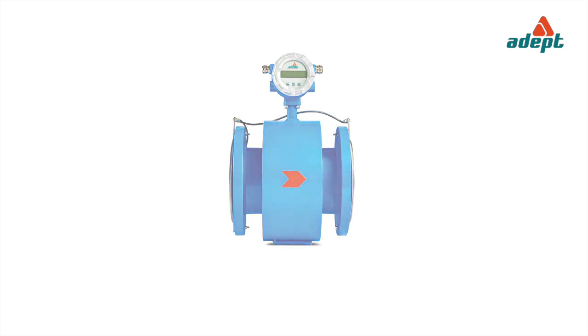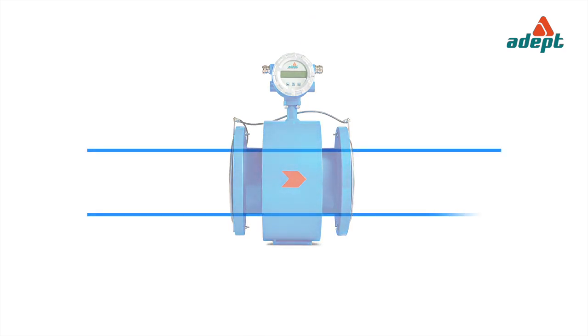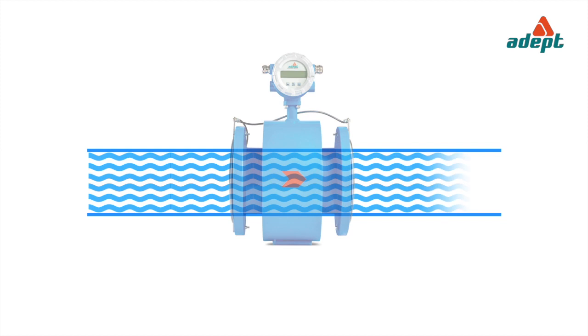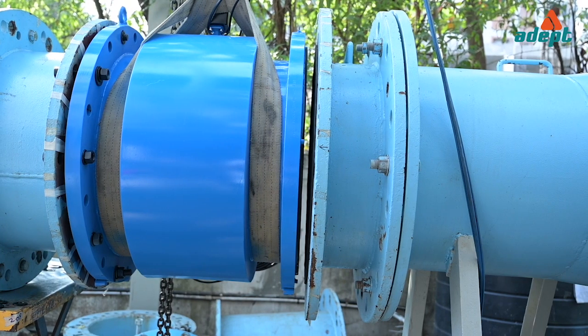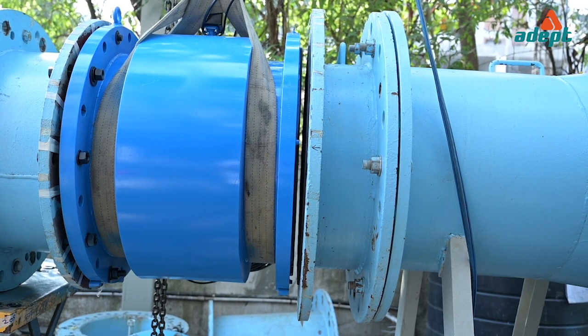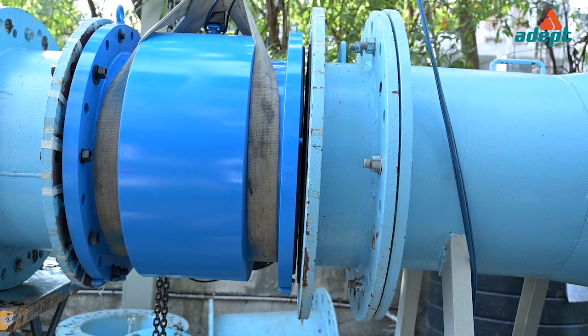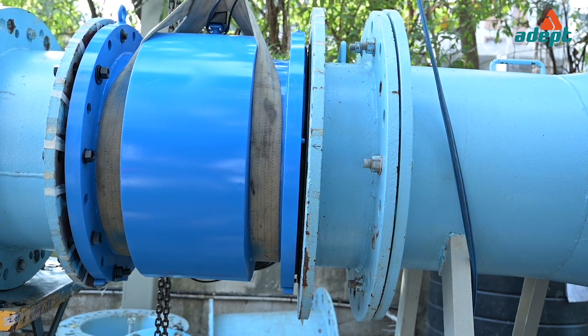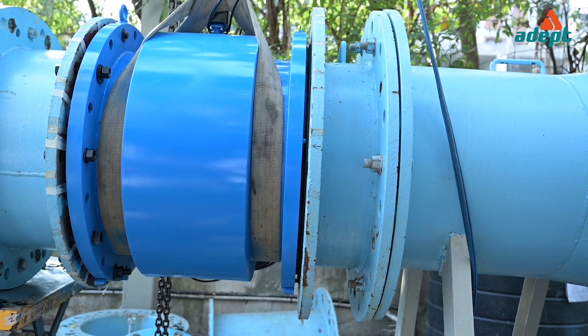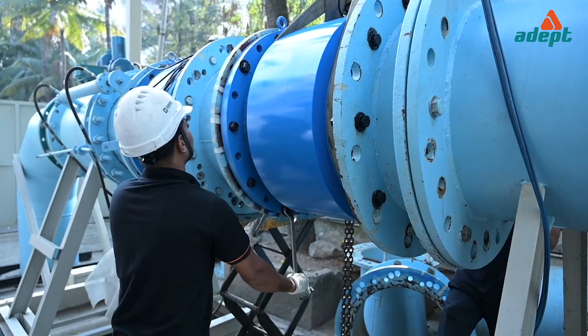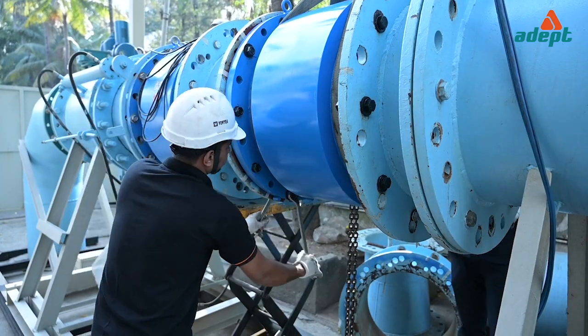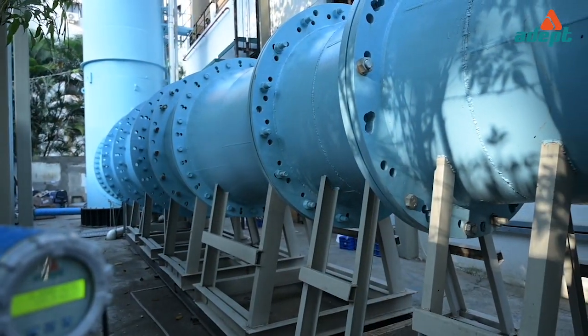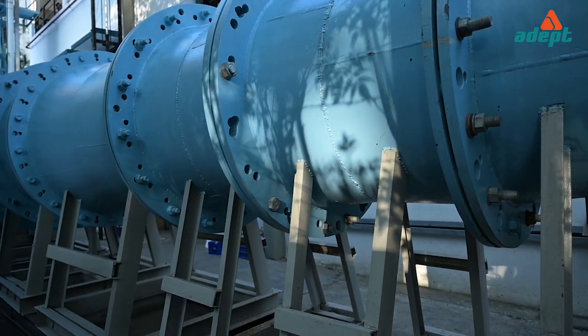Once the flow tube has been mounted, fill the pipeline gradually, preferably with water instead of processed liquid, and confirm that the entire mounting is leak-free. Even if minor leaks are noticed, check the axial alignment of the flow tube with the upstream and downstream pipe lengths, cleaning of the gasket, the rating of the gasket material and proper tightening of the bolts. After eliminating the leakage, allow the process liquid to pass through the pipeline.